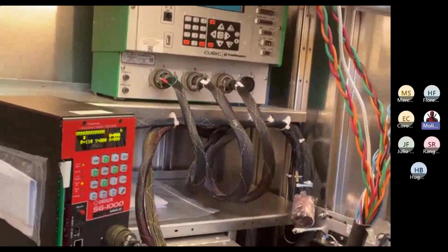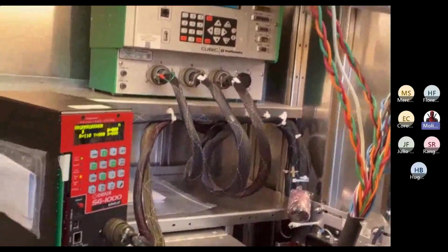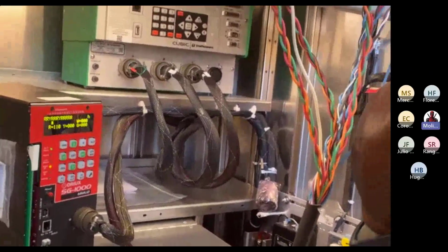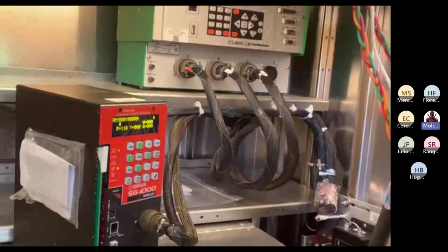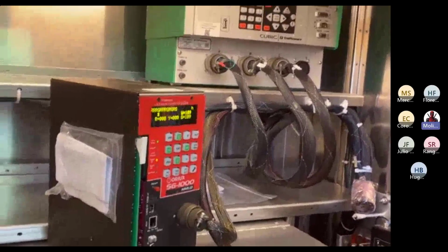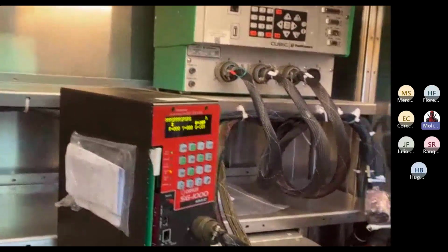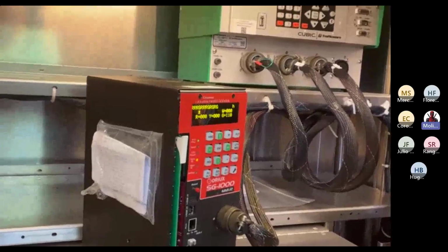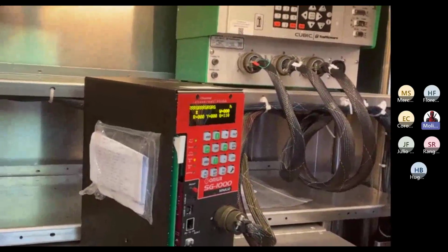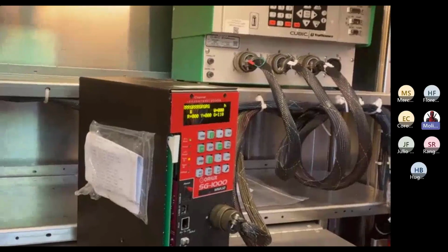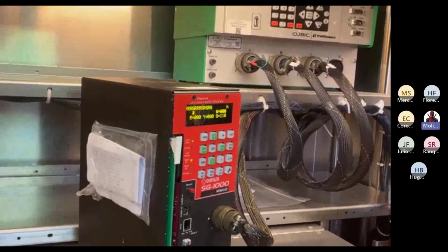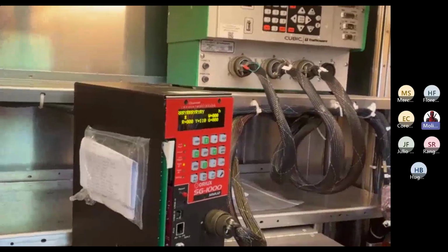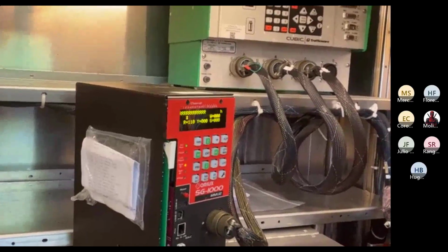Now, with power protection, you've got a lot of connections coming into the cabinet. A lot of times on the outputs, down at the terminal facility where you're connecting the signals, lightning can strike a pole, hit the signal, and go through that wire into the bottom of this back panel. So a lot of times you'll have the fuses or MOVs on the outputs to protect from that. It'll burn those up. But it depends on whether your area has a lot of issues like that. It's different from place to place.